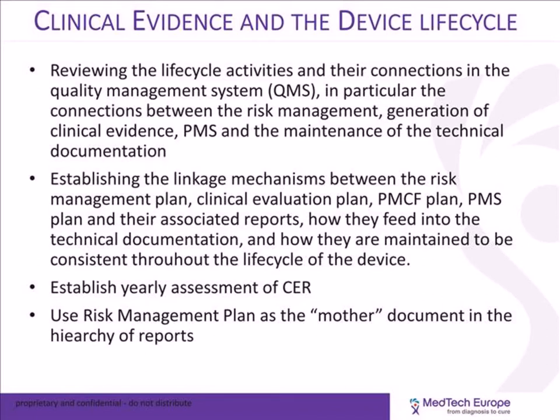A second point I want to emphasize is establishing the linkage mechanism between all these plans: the risk management plan, clinical evaluation, post-market clinical follow-up, and how they feed into the technical documentation to be maintained through the life cycle of the device. Establishing a yearly assessment of the clinical evaluation report, specifically for Class 3, is something that we believe is key to be planned.